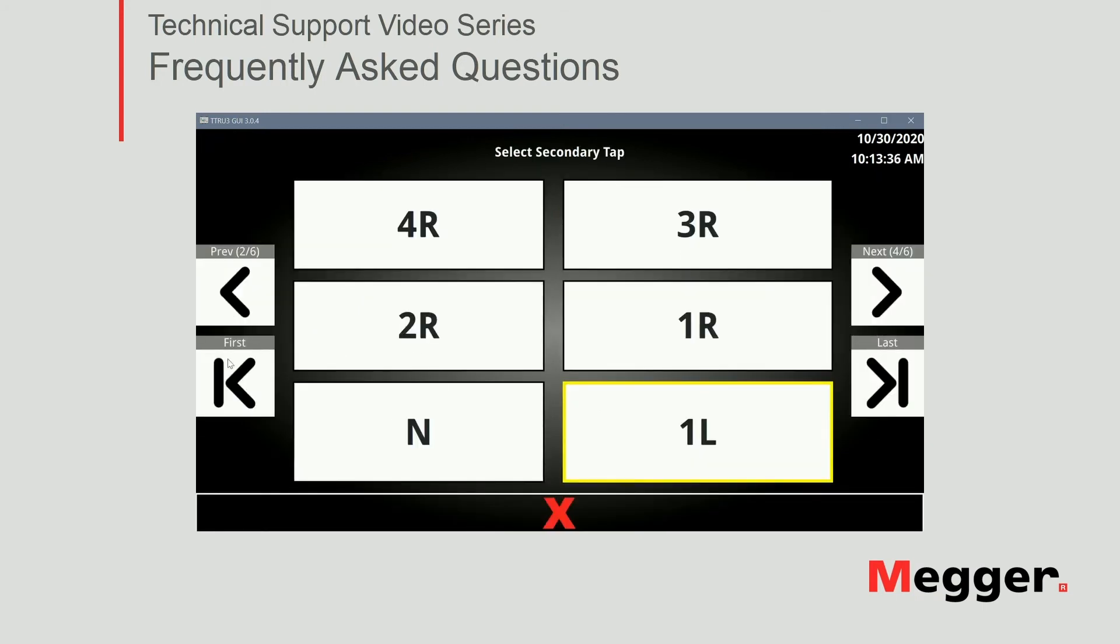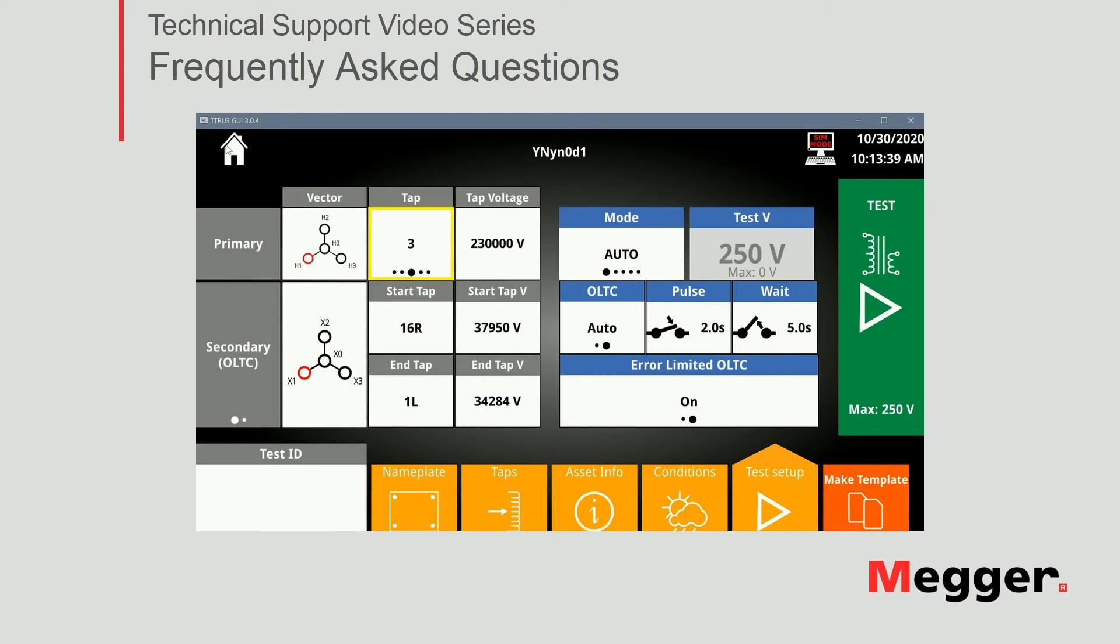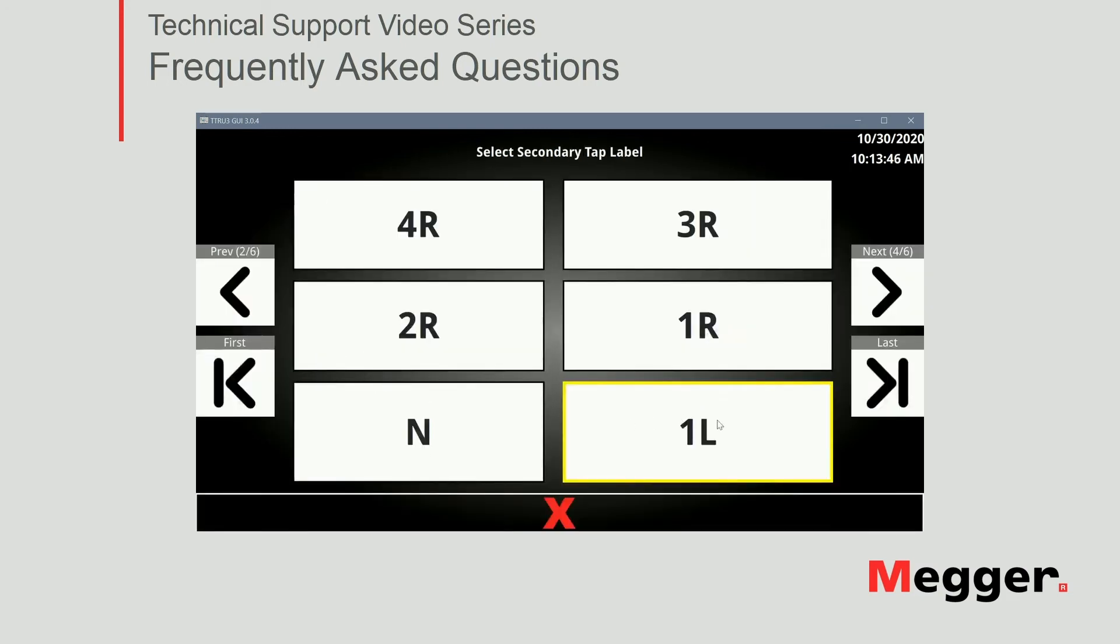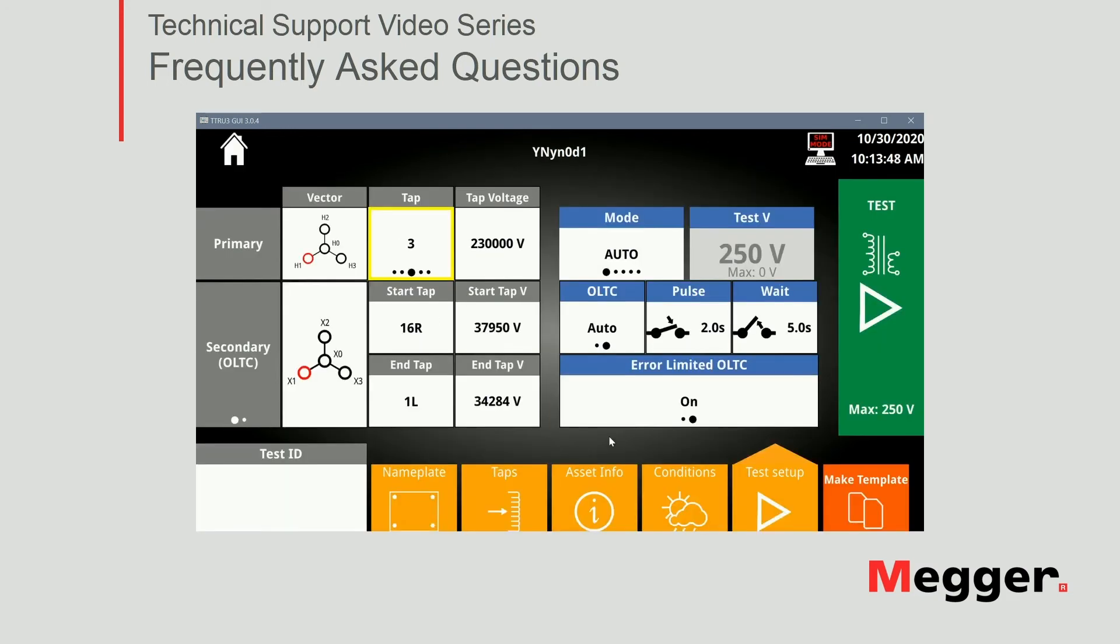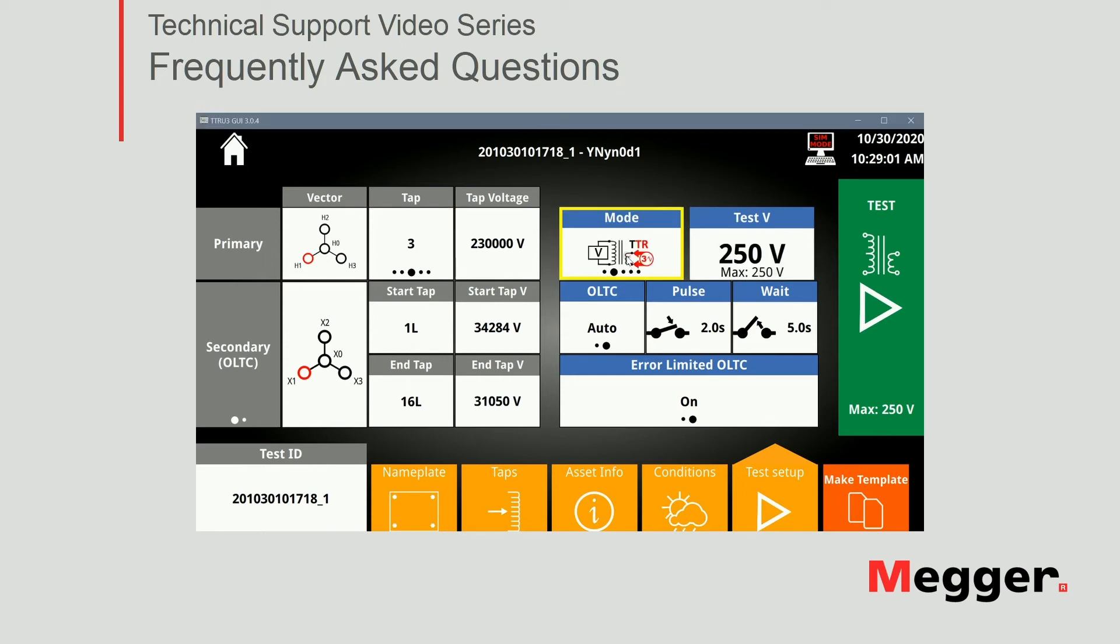And I want to tell the software that I want to start at the very top, right? According to my nameplate, 16R, 16Race. And I want to end at the very last. I do want to test all positions. I can also define the test mode from the different options available. Auto is automatically selected. But I do have the option to change from step up, step down, single, and three-phase test mode. So I recommend to leave it in Auto as the unit will select the best option for the transformer.